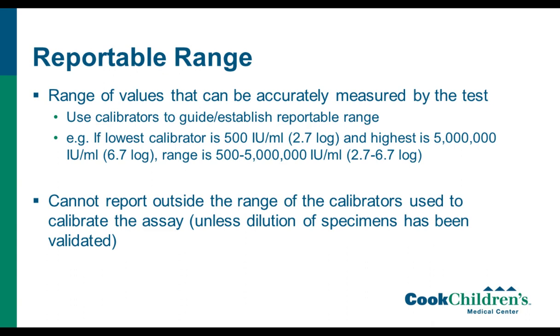You cannot report outside the range of calibrators unless you validated that. So for example, on ours, if we would get, in the example I mentioned above, something that was greater than 5 million, we simply report that as greater than 5 million. You can do further validation studies to dilute a specimen and be able to give it a specific value. That does require further validation, but that does allow you to report outside of the range of those calibrators.